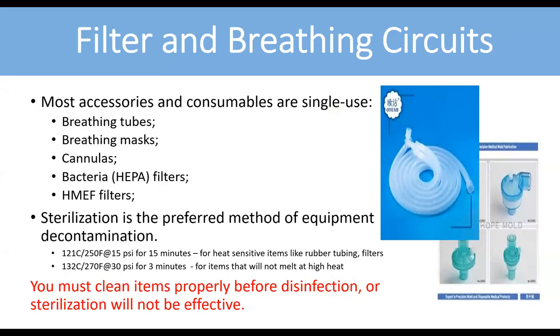Filters and breathing circuits - most accessories are consumable, single use items: breathing tubes, breathing masks, cannulas, bacteria filters (basically HEPA), and HME filters. Most of them are single use, though some breathing tubes are multiple use and need to be sterilized. The sterilizing temperature is 121 degrees at 15 psi for 15 minutes, or 132 degrees at 30 psi for 3 minutes, depending on the type of reusable circuit.